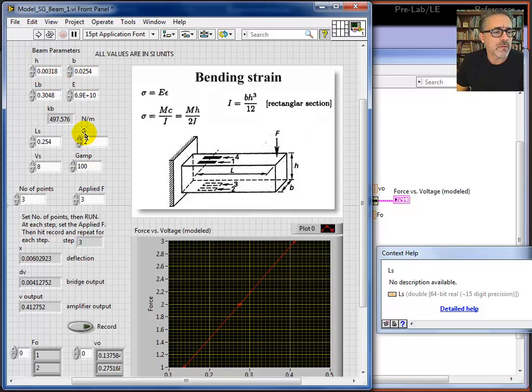We've got beam parameters, and then we've also got instrumentation parameters here. The gauge factor of each gauge, the amplifier that's applied at the output of the bridge, voltage input into the bridge itself, and then the location to the strain gauges. All these can affect what the output is. And here's where you enter applied force.